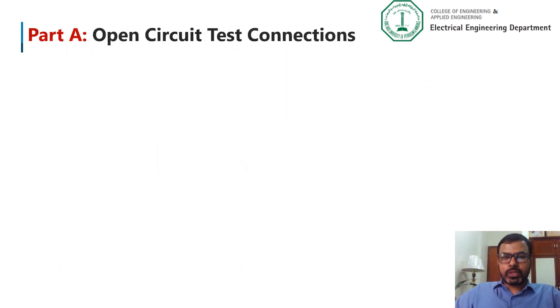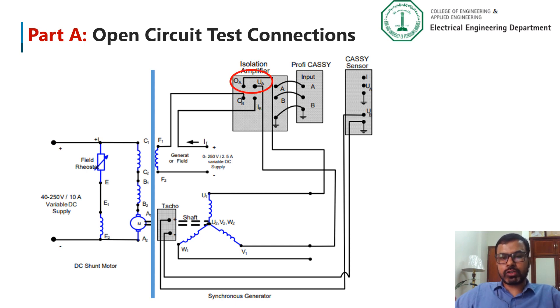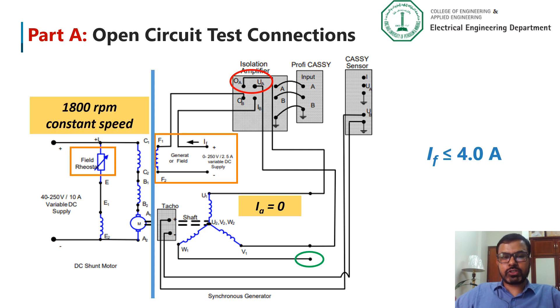In today's experiment we have two parts. In the first part we will study the open circuit characteristics of the synchronous generator. Here is the open circuit test connection. On the right side we have the connection for the synchronous generator, and on the left side we have the connection for the DC shunt motor. From the circuit, terminals U1 and V1 of the synchronous generator are connected to a voltmeter, whereas terminal W1 is not connected to anything, so there will be no armature current flowing. To see the voltage buildup, we vary the field excitation, which should not exceed 4 amperes. Speed must be kept constant at 1800 RPM by varying the field rheostat of the motor.